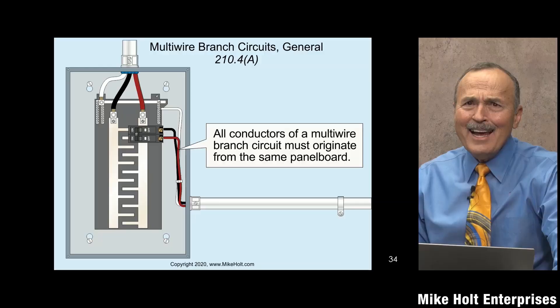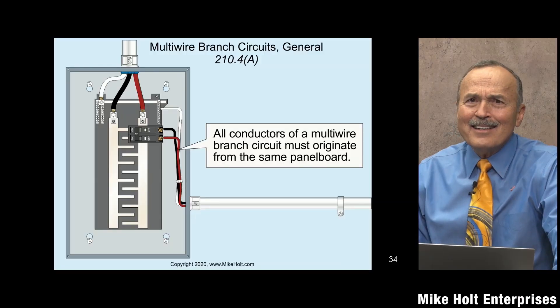A lot of people jump right past this rule, but this is something important. In a nursing home, a patient reported a problem, a breaker tripped, and it took three hours to find the breaker — which was on a different floor. There was neutral sharing involved. It was a disaster. It can cause a nightmare.